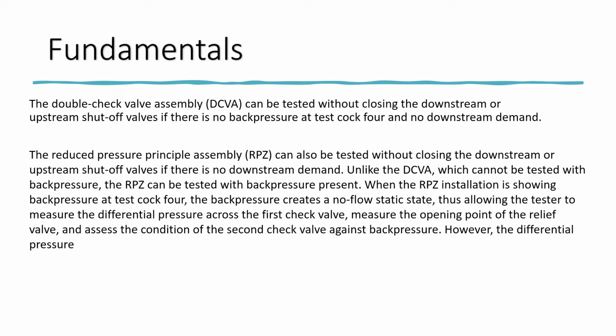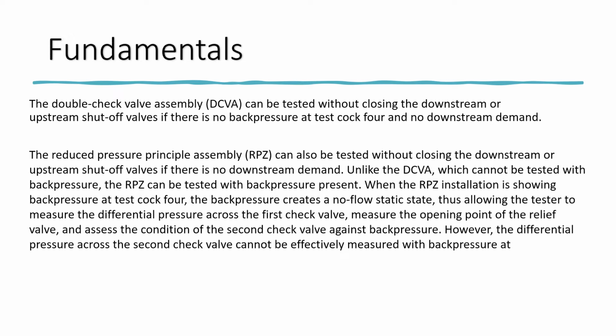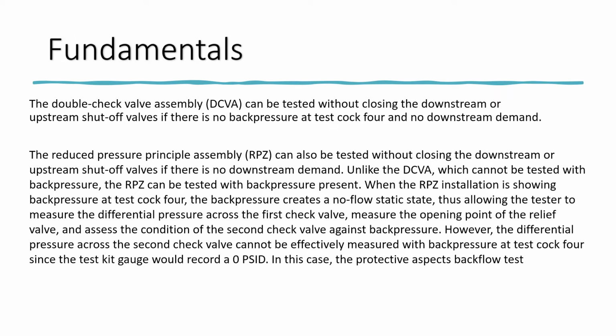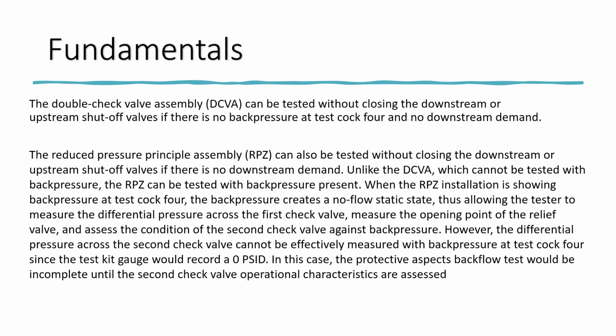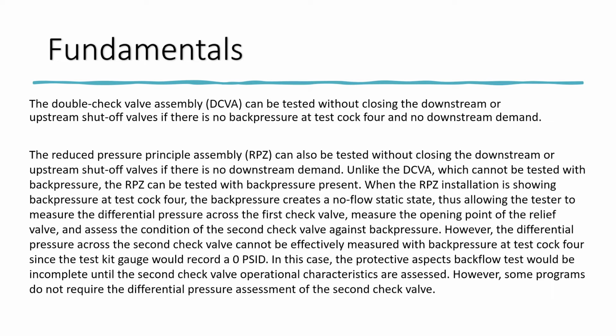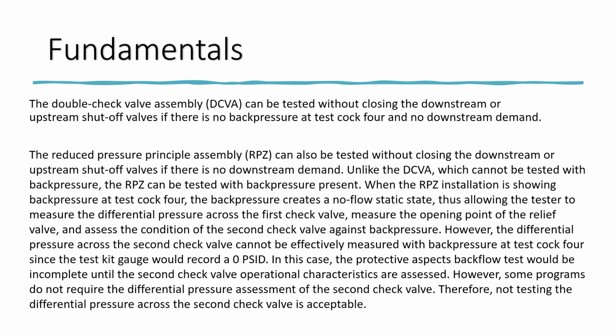However, the differential pressure across the second check valve cannot be effectively measured with back pressure at test cock 4, since the test kit gauge would record 0 PSID. In this case, the protective aspects backflow test would be incomplete until the second check valve operational characteristics are assessed. However, some programs do not require the differential pressure assessment of the second check valve. Therefore, not testing the differential pressure across the second check valve is acceptable.